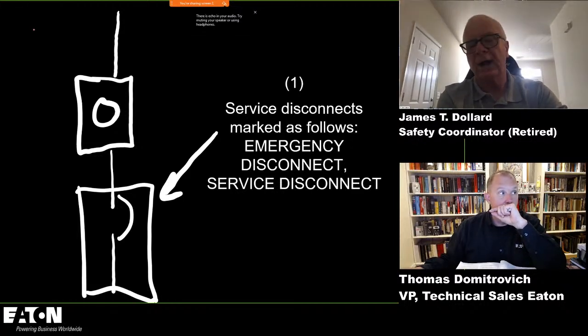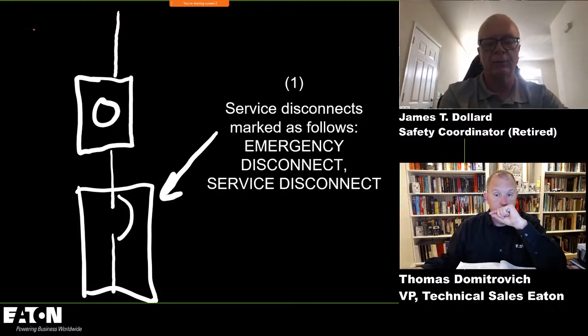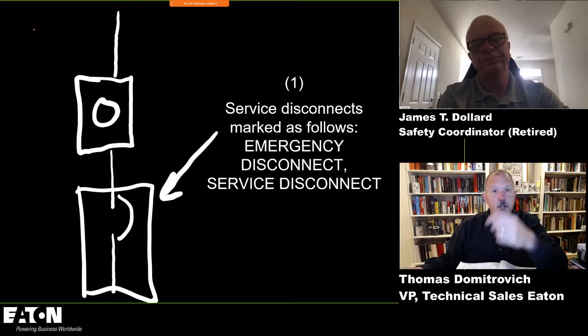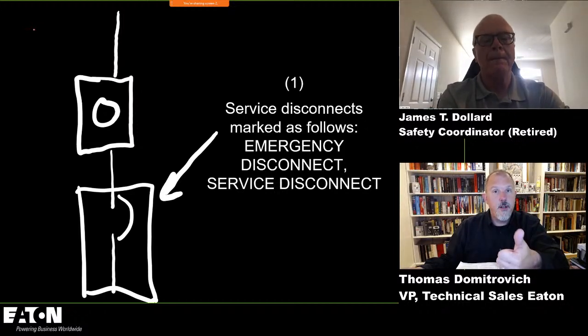Yep. And then we've got requirements for optional standby systems. If you've got an optional standby system, you're going to have to put a sign right next to the emergency disconnect. So now I'm the fireman. I get there, I open that service, but I know that I've got an optional standby system, which could start when I open the service, but it tells me where it is so that I can go kill the prime mover. That's right.